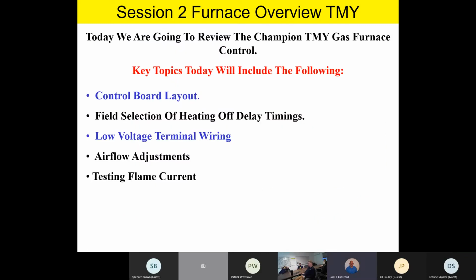And so today we're going to be reviewing the gas furnace control board again, and some of the things we're going to be talking about specifically will be the control board layout. Now, team, we're going to actually go over every input and output on that board. We're going to talk about field selection of heating off delay timings, as well as low voltage terminal wiring. And so literally every thermostat wire and where it lands on that board we're going to be discussing this morning.